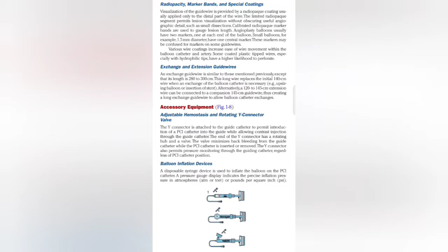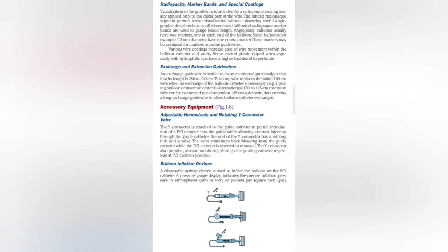Exchange and extension guide wires. An exchange guide wire is similar to those mentioned previously, except that its length is 280 to 300 centimeters. This long wire replaces the initial 140 centimeter wire when an exchange of the balloon catheter is necessary, for example, upsizing the balloon or insertion of a stent. Alternatively, a 120 to 145 centimeter extension wire can be connected to a companion 145 centimeter guide wire, thus creating a long exchange guide wire to allow balloon catheter exchanges.